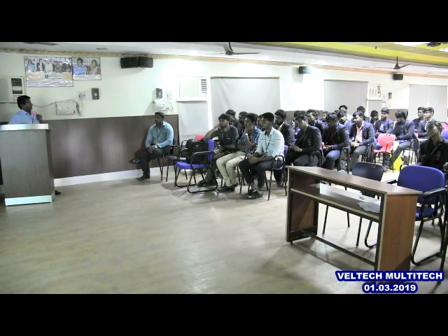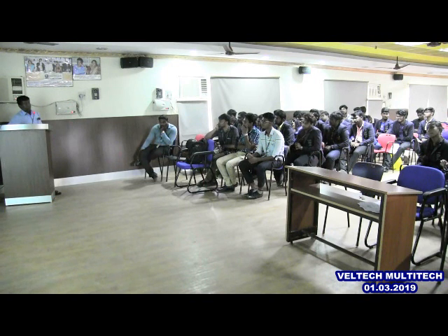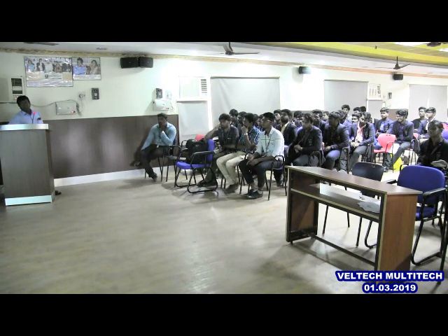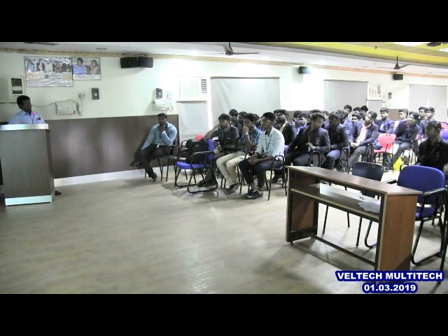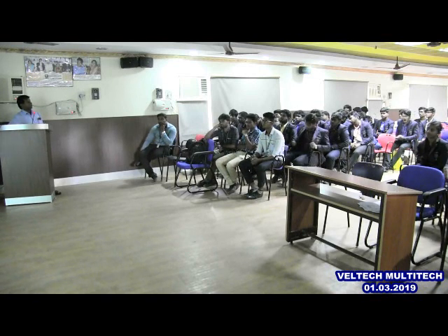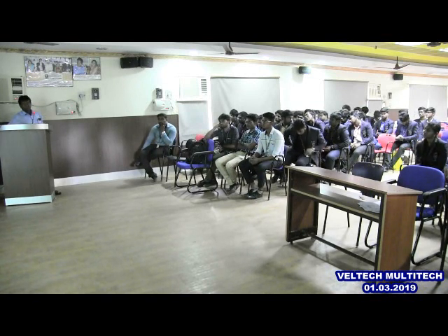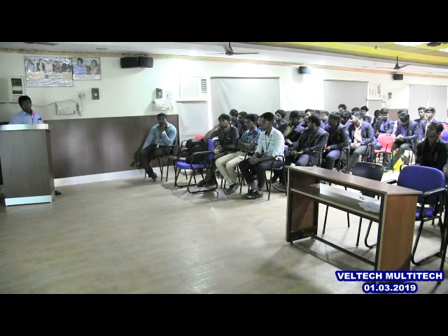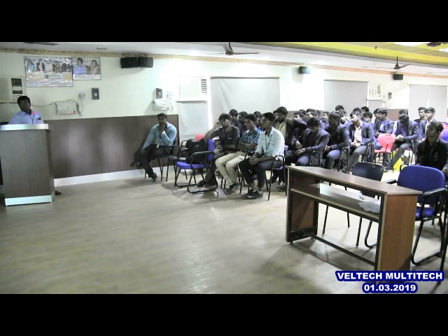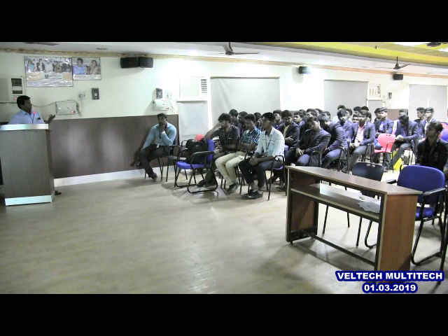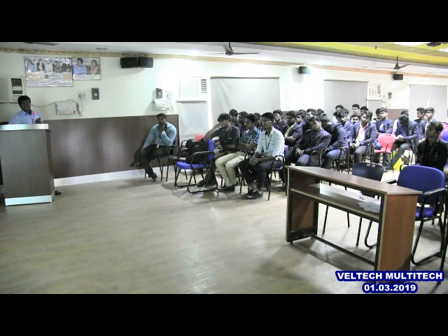So we can say why we have to invest such an amount. It may be some 2-3 crores we have to invest for achieving and maintaining a clean room. See what that is? People have classified, there are international standards for categorizing clean rooms. So class 1, 10,000, 1 lakh. Class 1 lakh means in a cubic volume of 1 foot by 1 foot by 1 foot, how many particles are there of size 0.5 micron? That is how they classify.